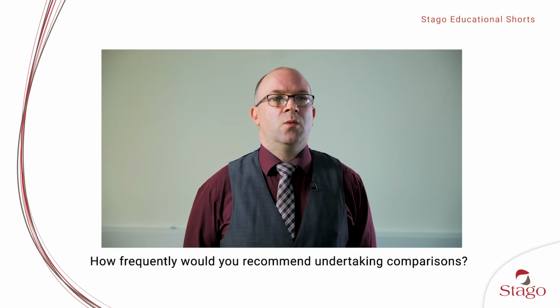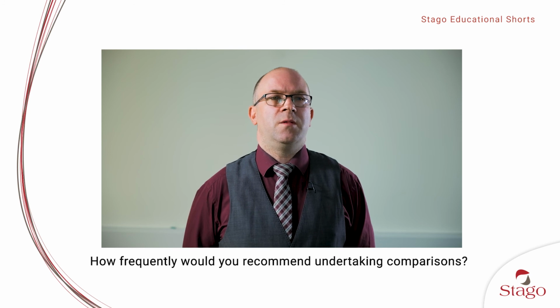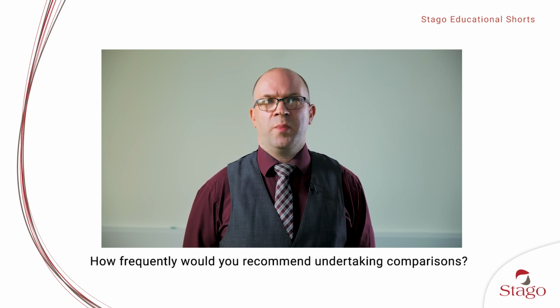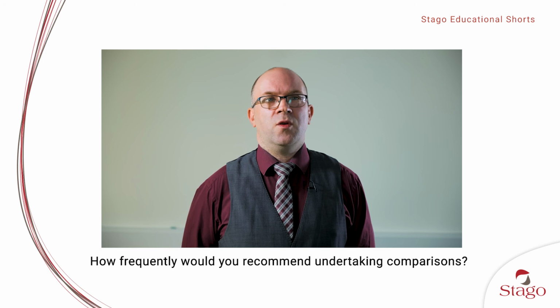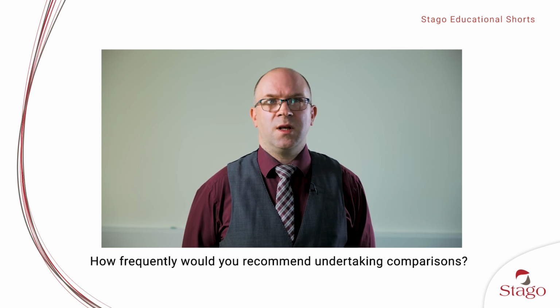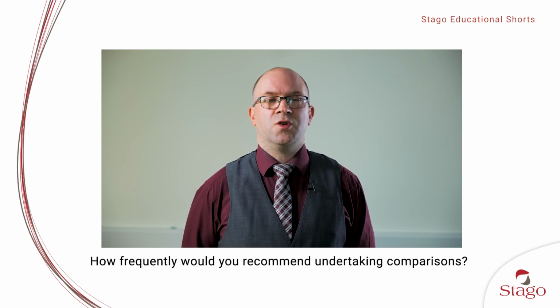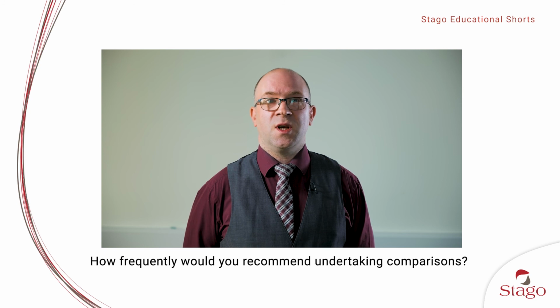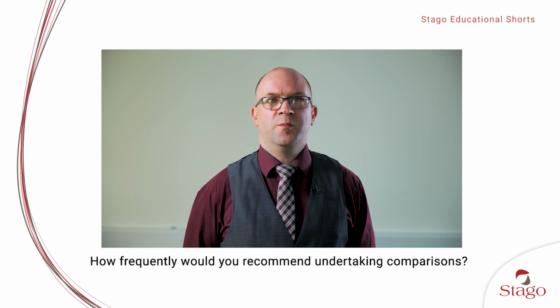Some things will need to be done more regularly, and that'll be based on whether you've demonstrated non-comparability in the past, whether you've had issues with your EQA, whether you've had issues with your IQC, whether you see drift in your measurement uncertainty. All of these things, as I tried to show in the first slide, are all dovetailed into each other. They're all linking together. So it's not a one-size-fits-all. It's an overall quality management process.